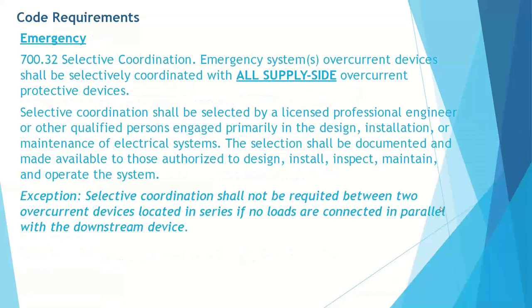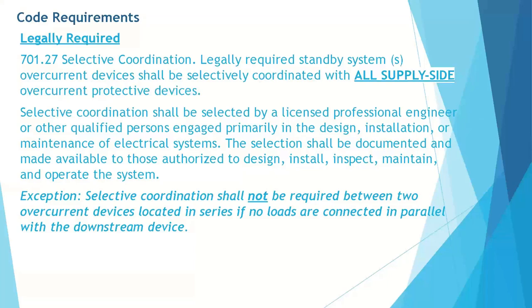Accomplished by the selection and installation of overcurrent protective devices and their rating or setting for the full range of available overcurrents, from overload to the maximum available fault current and for the full range of overcurrent protective device operating times. I want to point out that it is clearly defined now as the full range of current and the full range of time.